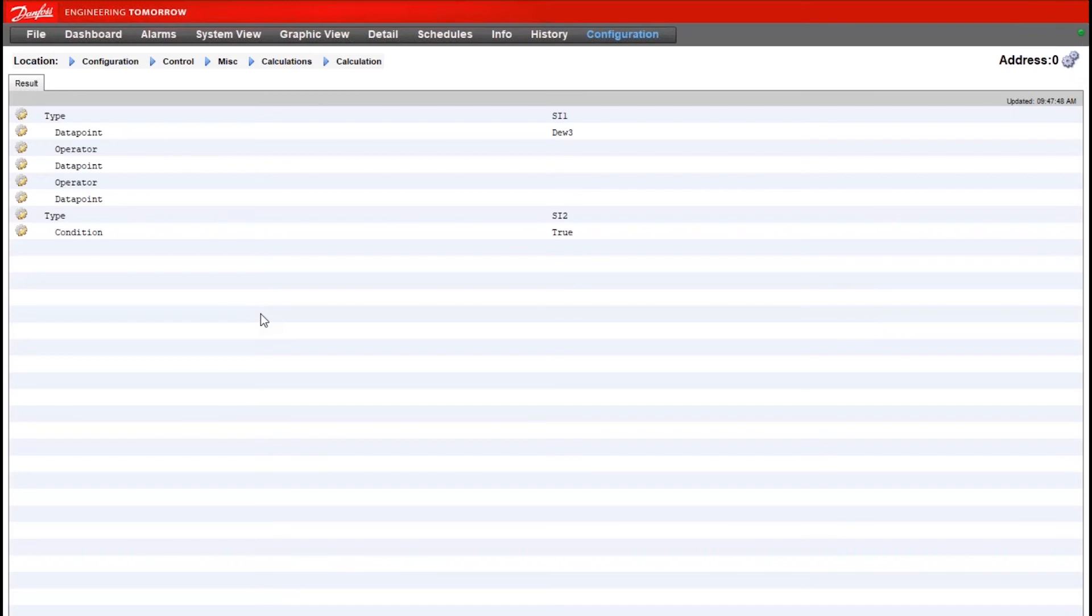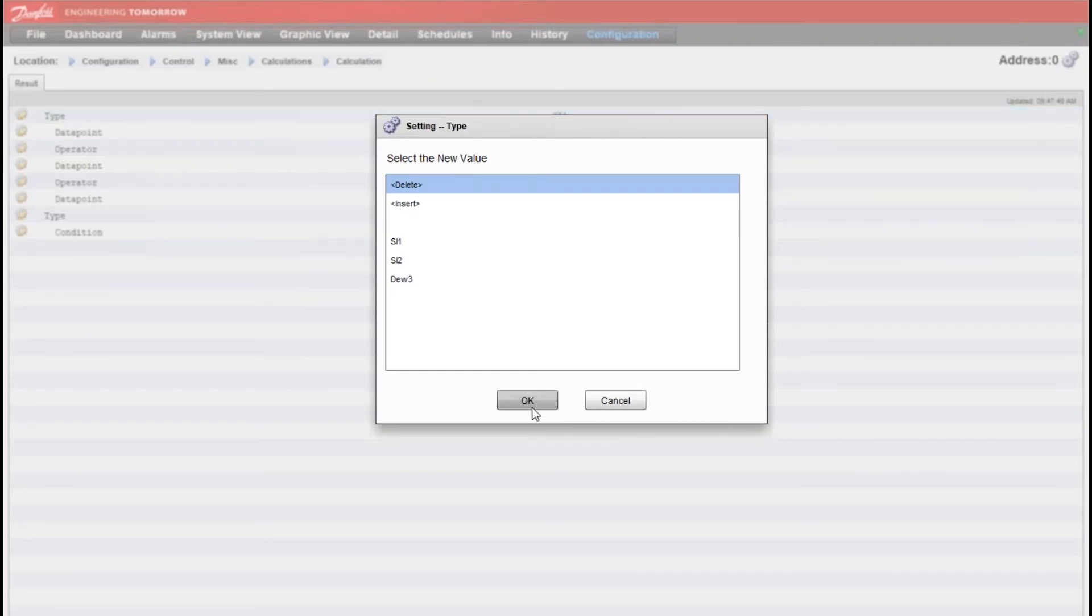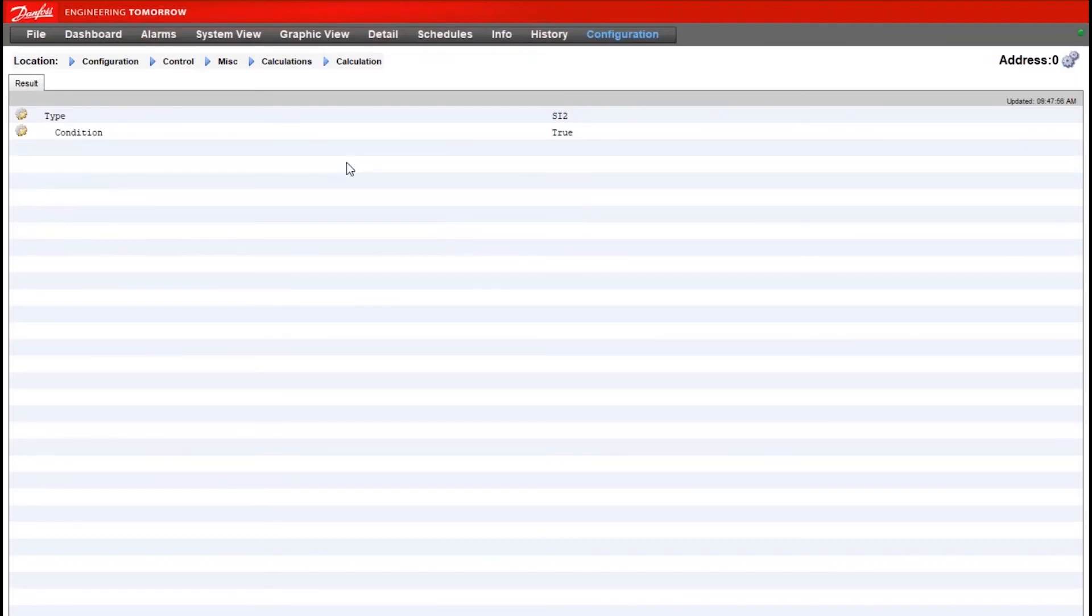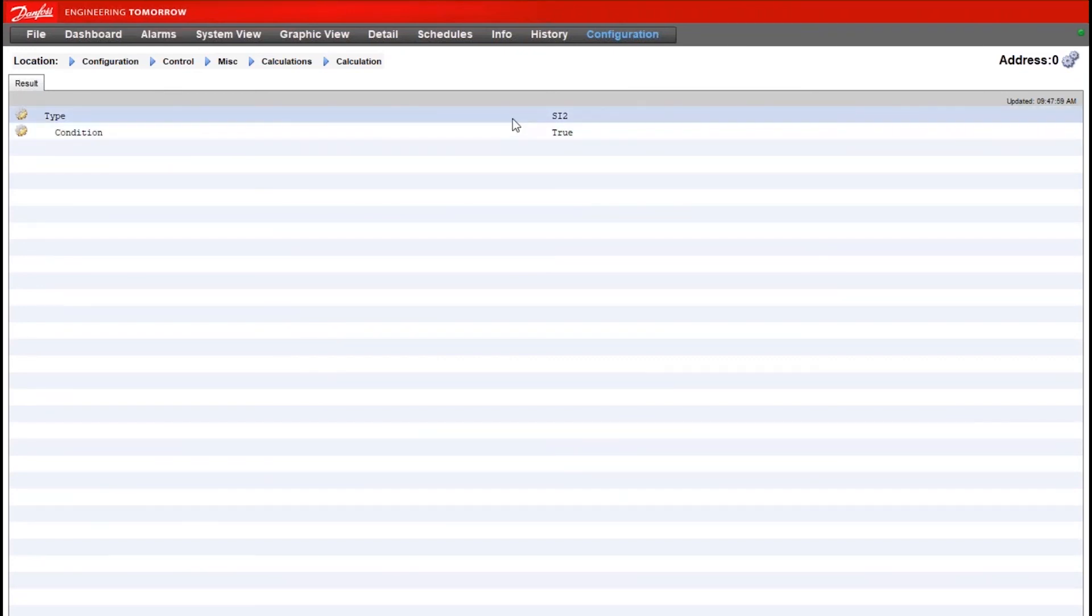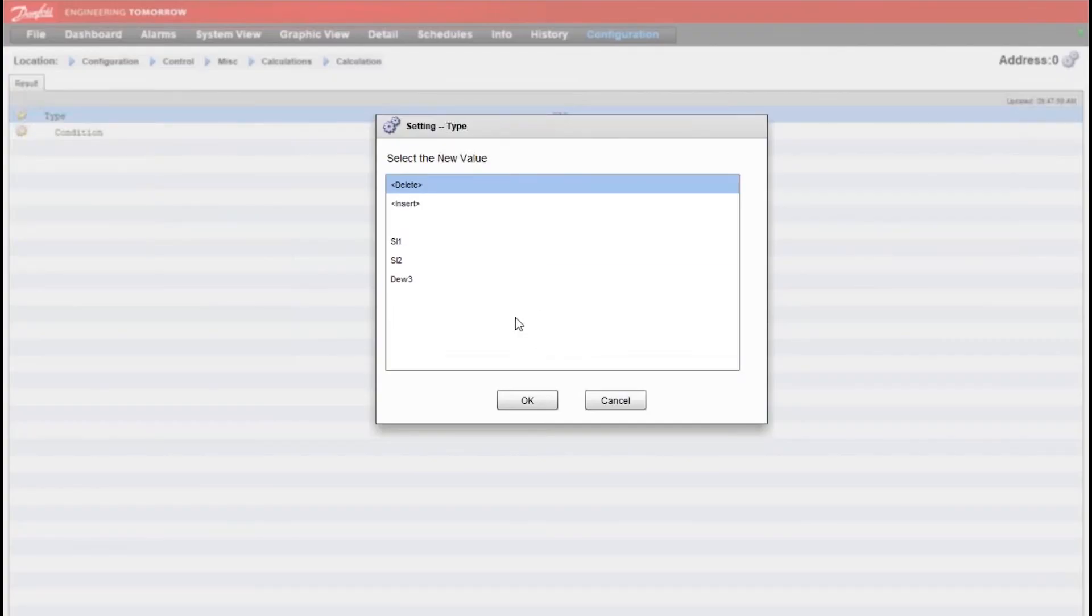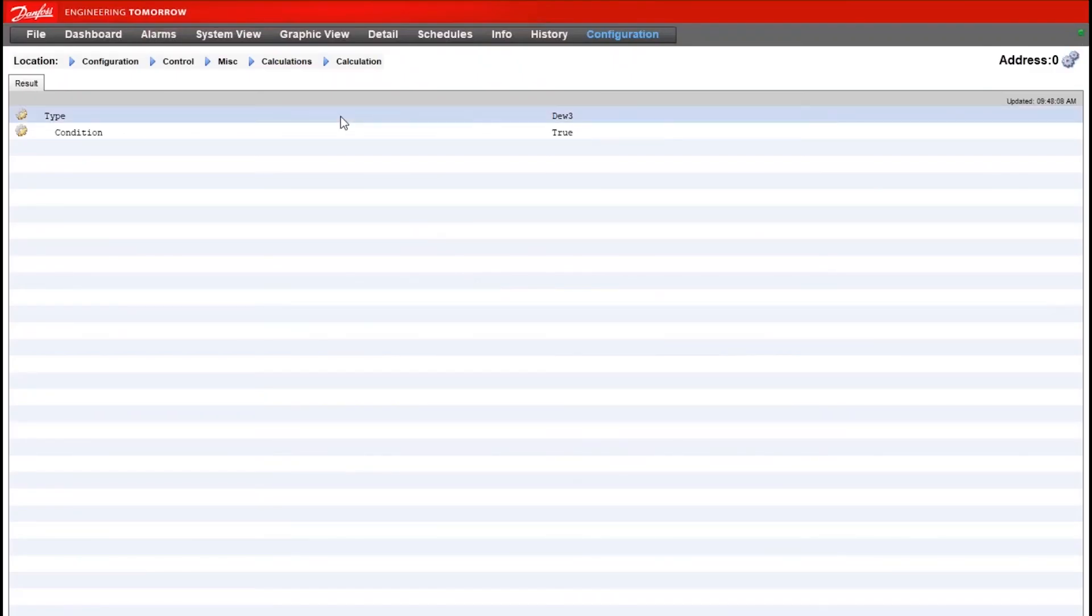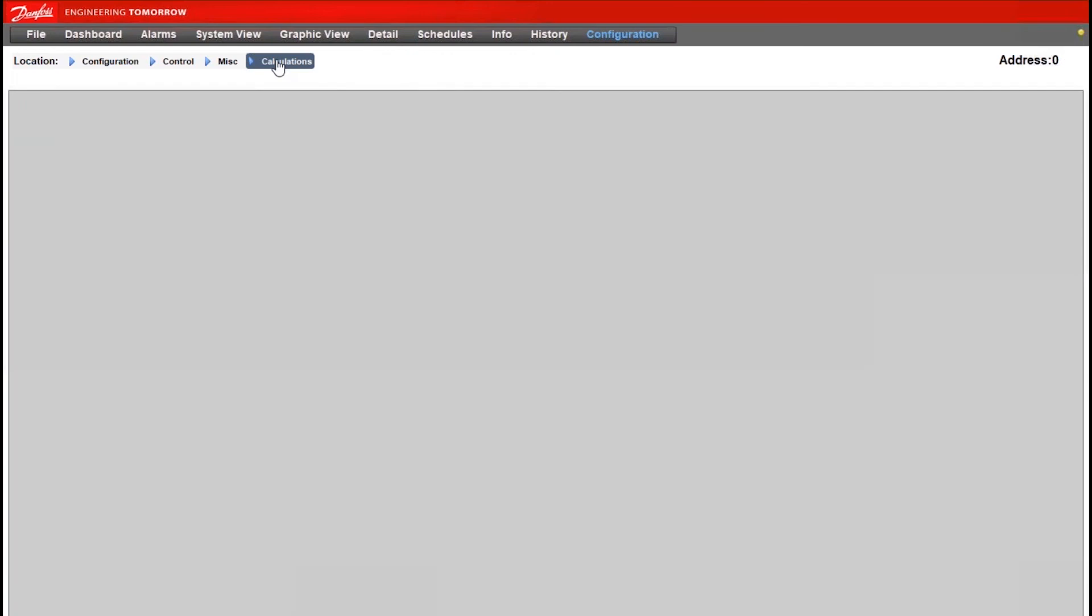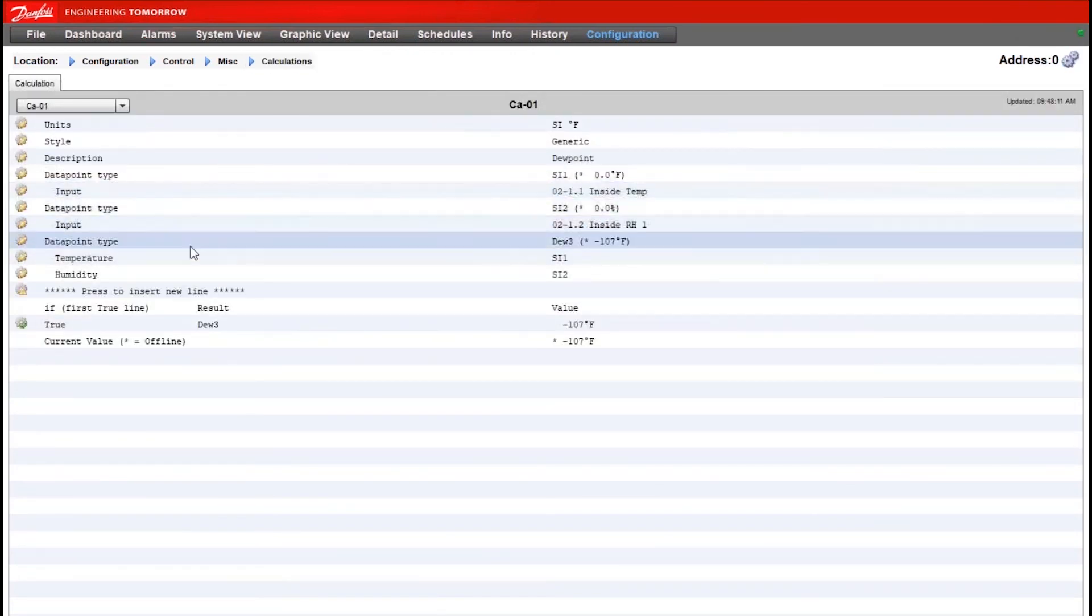I'll double-click here to get into our secondary screen to configure the results. I can delete this top option by double-clicking on the type line and choosing delete. And then for the remaining line, so true, we want to leave in place. The type we want to change to Dew3, which would be our dew point value on line—or data point type number three is where the number three comes from.